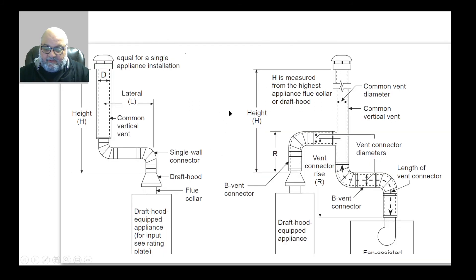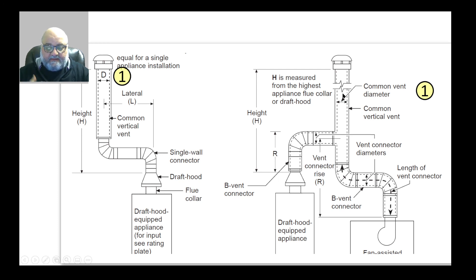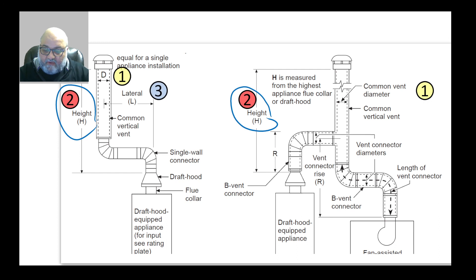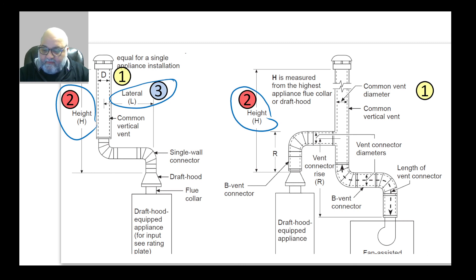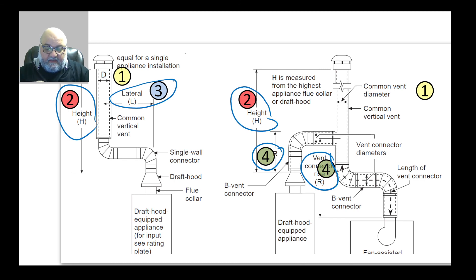For sizing purposes, there are four key measurements. Number one is diameter — that is what you are sizing, the unknown. The other three are given: height (in feet), lateral distance, and — if you have more than one appliance — the rise of each vent connector. For single-appliance applications you are given the lateral; for multiple appliances you are given the rise for each vent connector.